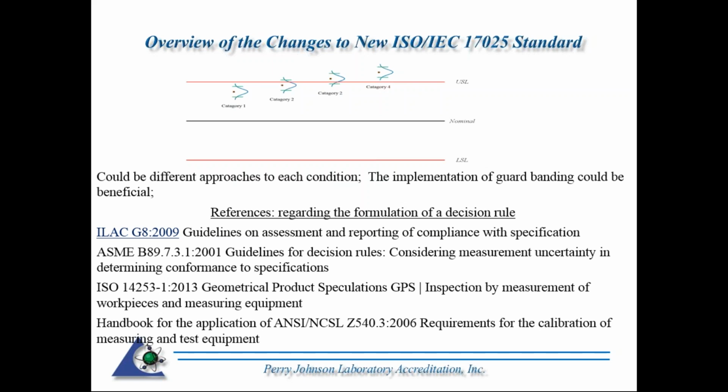So in that first category, we can see the point and the gray area are clearly in the accept. Hence, that could definitely be a pass. The line above that, the point is passing. However, that gray area of uncertainty points it over to the failure. So we're not really sure if it actually passes or fails. So that's when we're taking measurement uncertainty into account. We can't clearly state a pass in that situation.